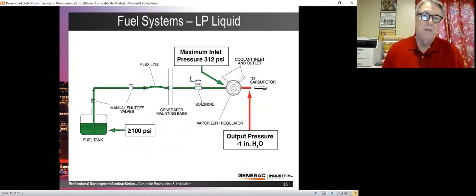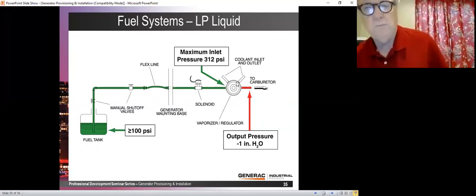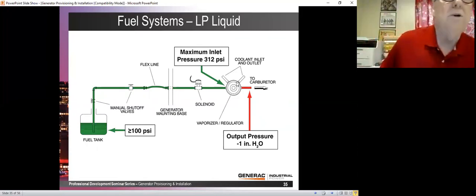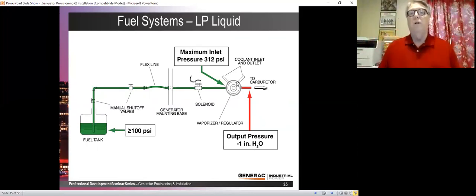In the liquid-based system, the pipe here, the fuel inlet, goes to the bottom of the tank, maybe a couple of inches, 1 or 2 inches off the bottom of the tank. And then you need to have a vaporizer. The vaporizer can either be on the tank or it can actually be in the generator. Vaporizers are not very expensive options, and you can order the generator with a vaporizer. It will, of course, have to have a block heater if you have a vaporizer.